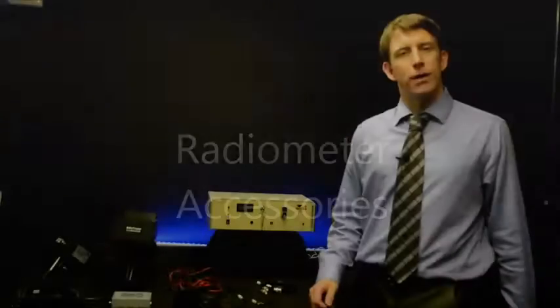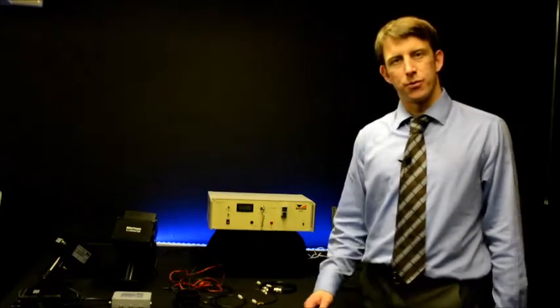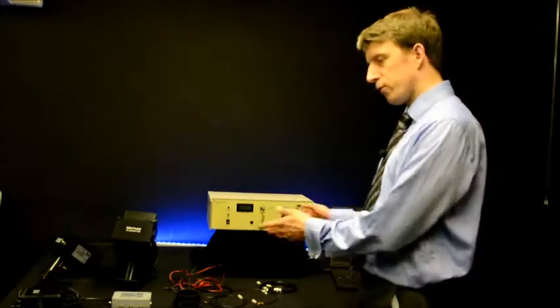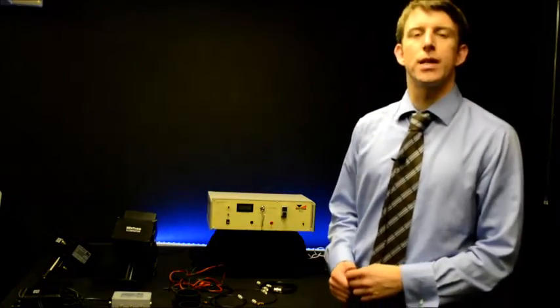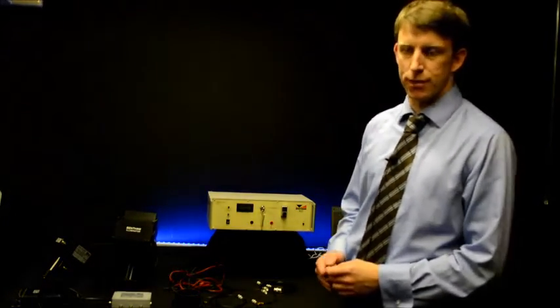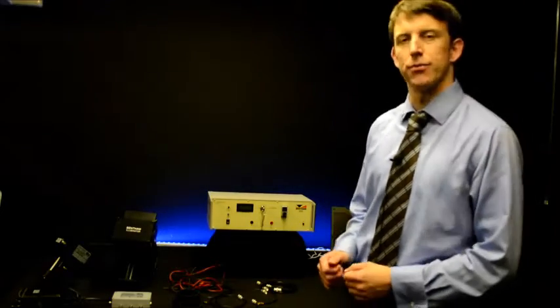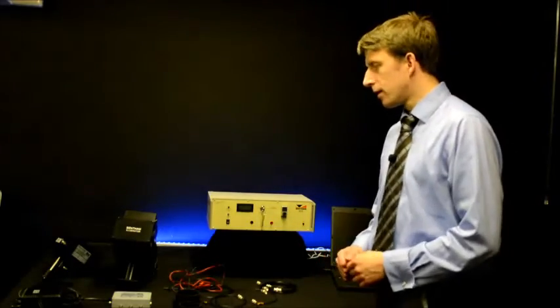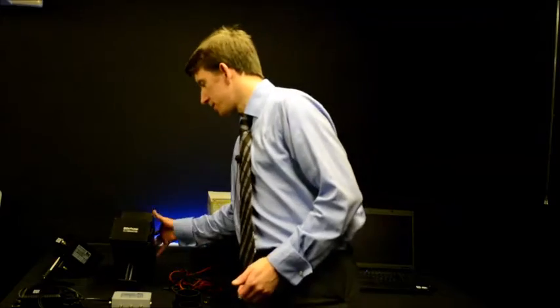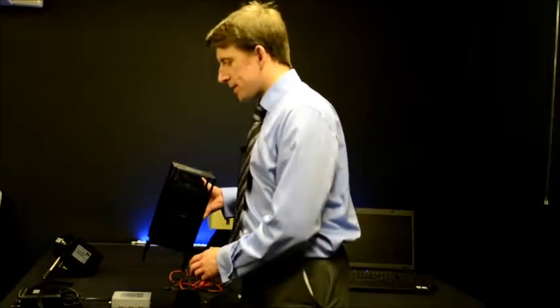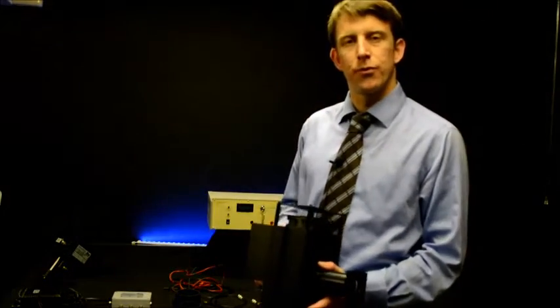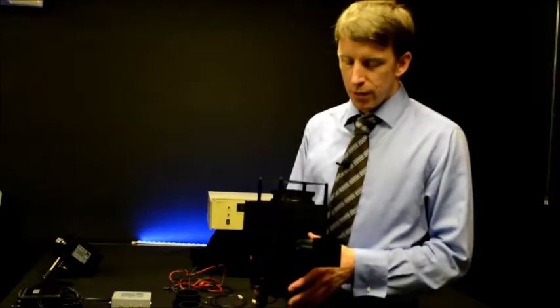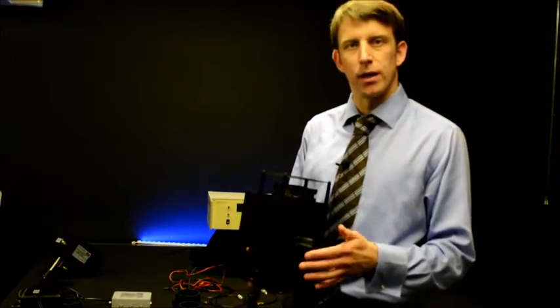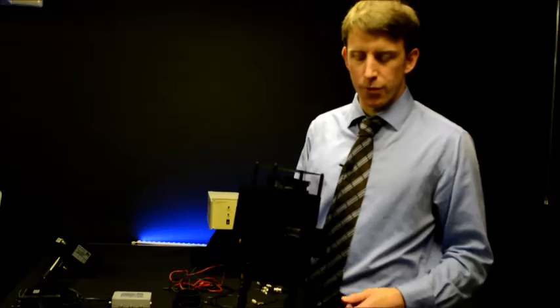Now we will look at the accessories of the radiometer characterization suite, all of which can be used with both the DTMC 300 spectroradiometer and the DMC 150 spectroradiometer. The light source is the IL7 xenon source. This houses a 150 watt short arc xenon lamp with a condenser lens coupling light to the monochromator entrance port.